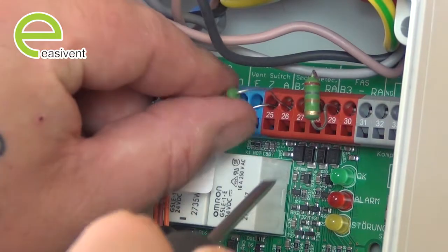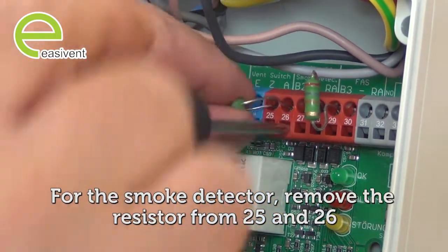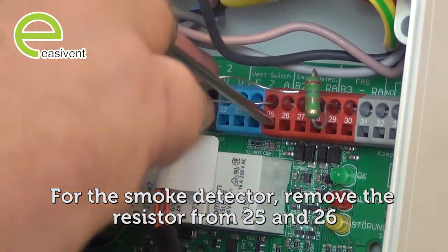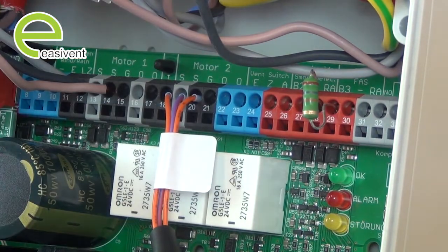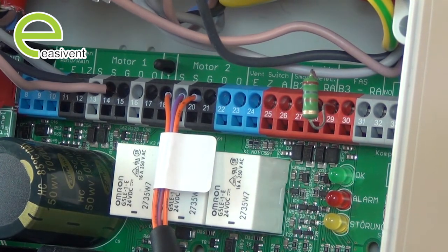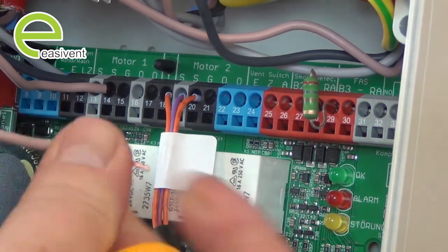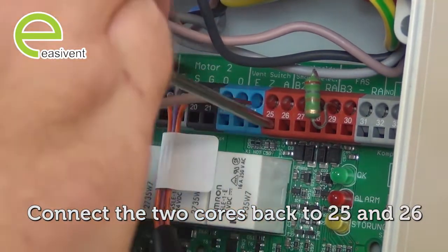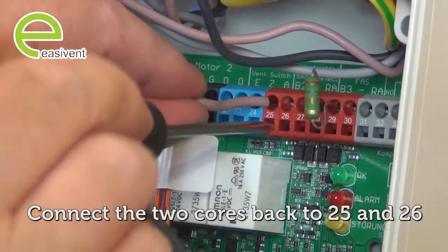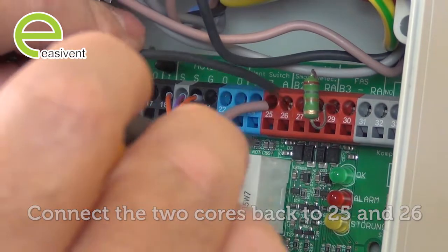For the smoke detector terminations, firstly remove the resistor fitted across 25 and 26 in the panel. That then goes across the base of the last smoke detector you're using, and simply connect two cores back to 25 and 26.